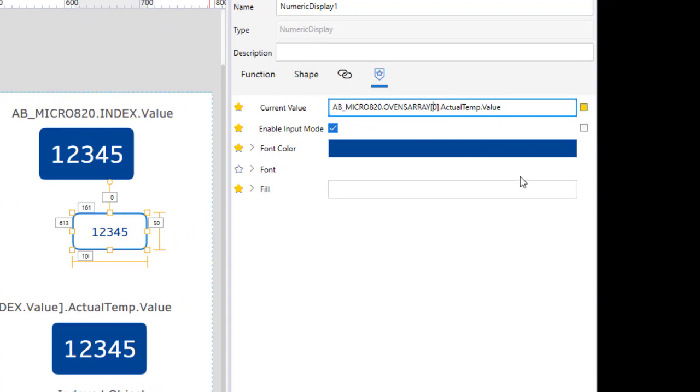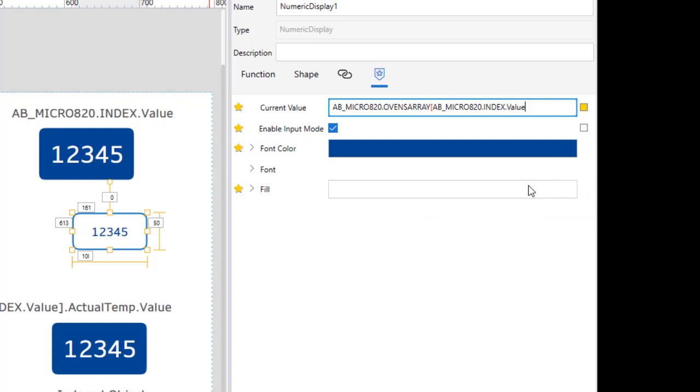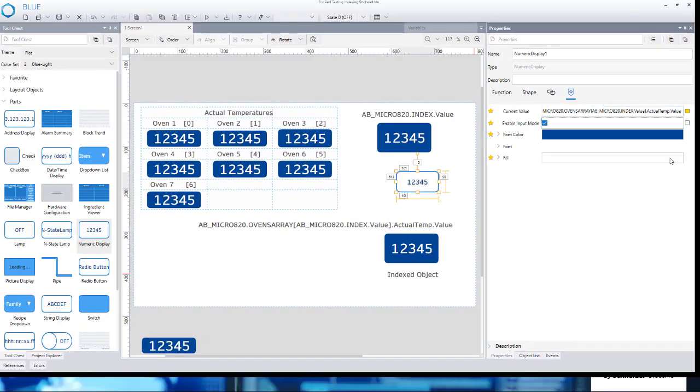Then in here we have to manually type in AB underscore Micro820 dot index dot value, then actual dot actual temp dot value. You can see there is some autofill available, and it took it, it's happy, it's not red.